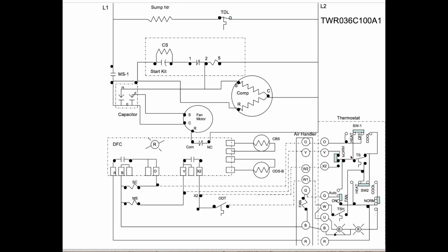Thermostat here, air handler here. We're just showing the terminal board and the fan relay there. Defrost board, outdoor unit, and so on. Okay, let's look at it before it's energized. We've got a sump heater or crankcase heater that's on here. This is on all the time until the temperature of the compressor reaches a certain temperature, and then it opens the crankcase heater.